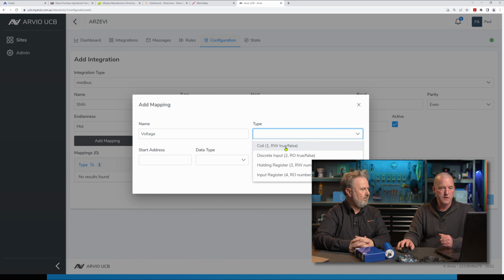So here you've got coil, discrete input, holding register, and input. You can see what they are: read/write true or false, read only true or false, read/write number, read only number. That'll be on the map you got from the manufacturer.